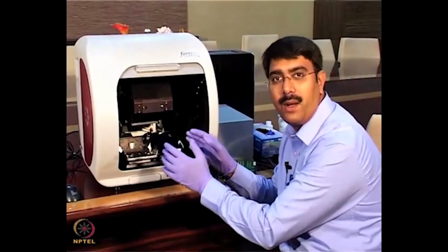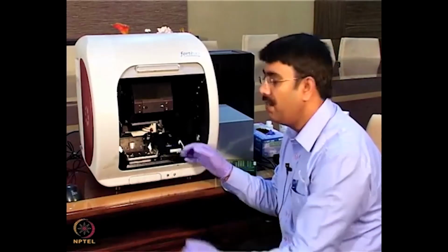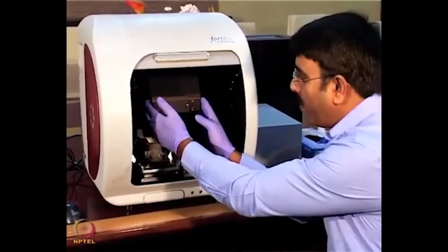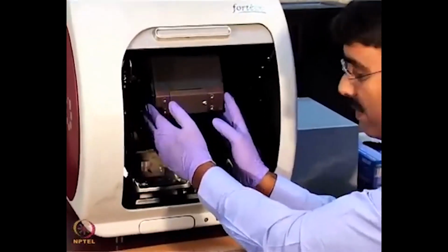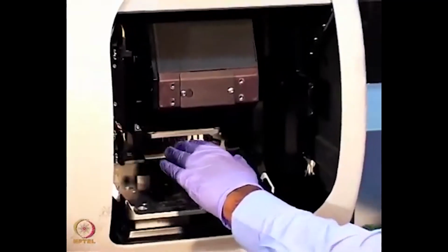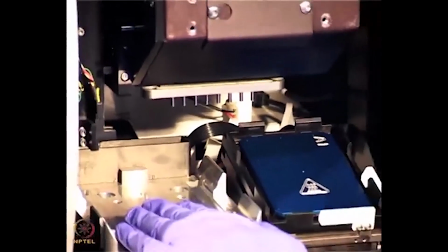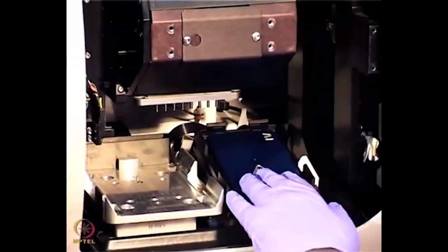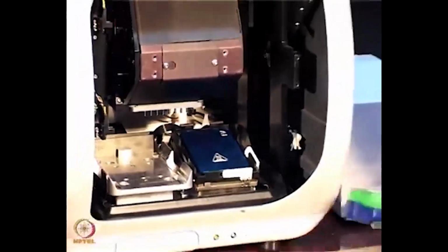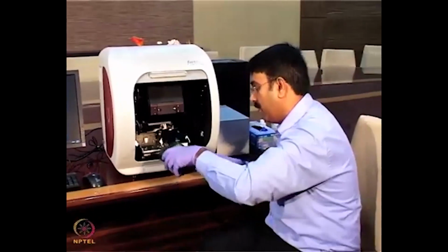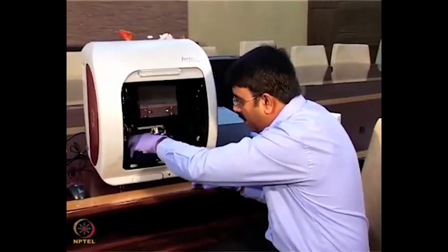This is the Pall ForteBio Octet RED96 instrument. If you look inside, we call this the optical head box. The optical head box consists of a spectrophotometer as well as the channels, or what we call a manifold. This is an 8-channel manifold, so it can take up 8 sensors. Here this is the sensor compartment, and this is what we call the sample compartment. Now you can see this is what we call the sensor holder, or sensor manifold.